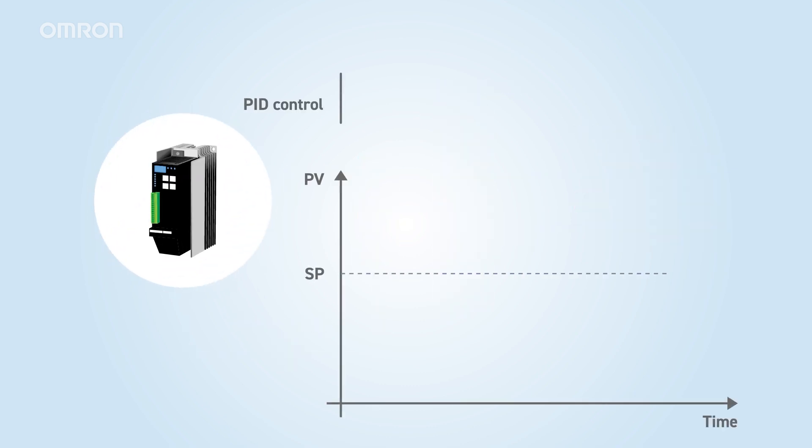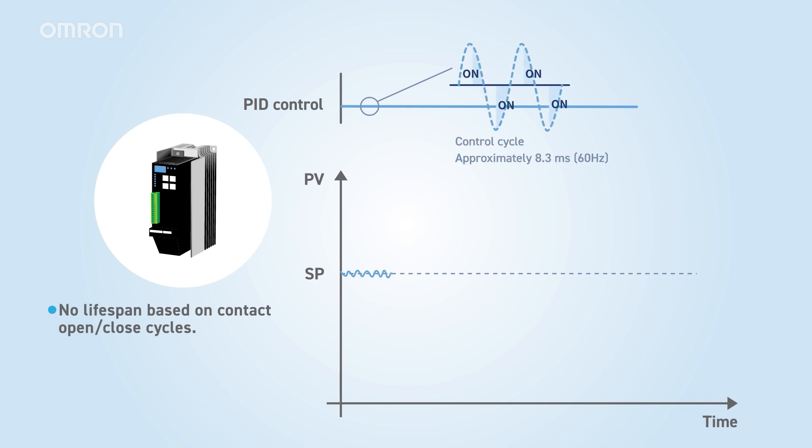Power controllers use semiconductor elements like SSRs, but can switch the heater on and off even faster. They can open and close once per half cycle of an AC power supply, about every 8.3 milliseconds at 60 hertz. For example, they are used with ceramic heaters for rapid heating. Many power controllers have a feature to suppress inrush current, making them suitable for controlling low-resistance heaters at room temperature such as lamp heaters. However, because they are more multifunctional than SSRs, they tend to be larger in size. They also generate heat and can produce noise, which may require countermeasures. Click here for the details about our power controllers.